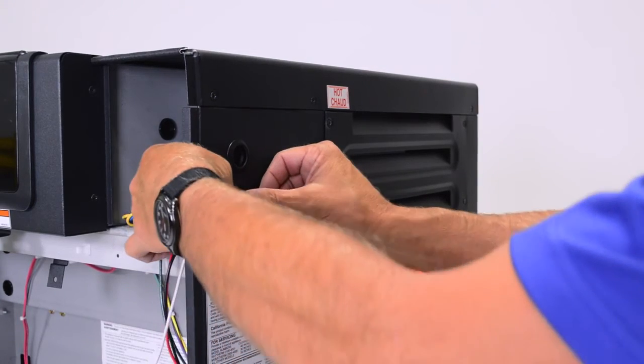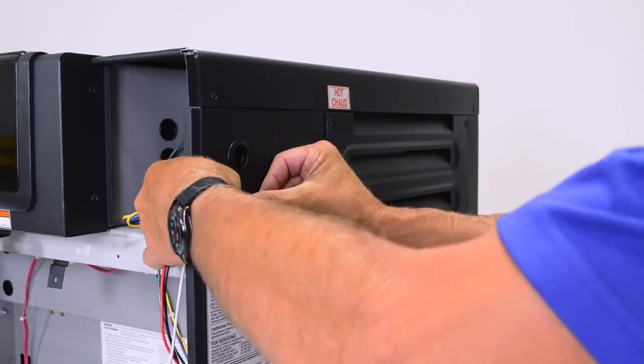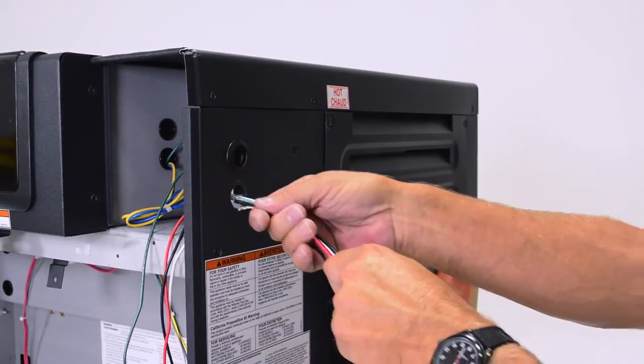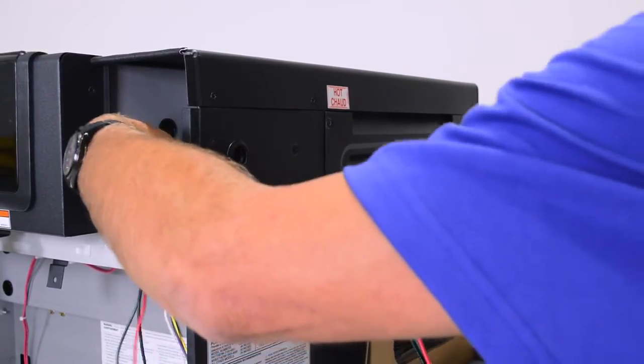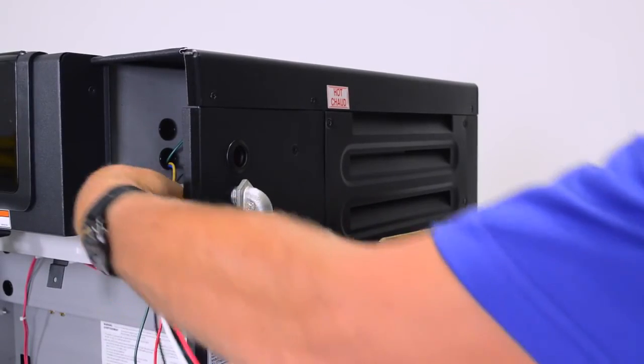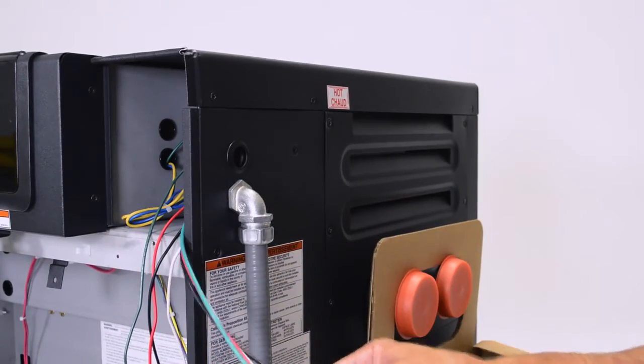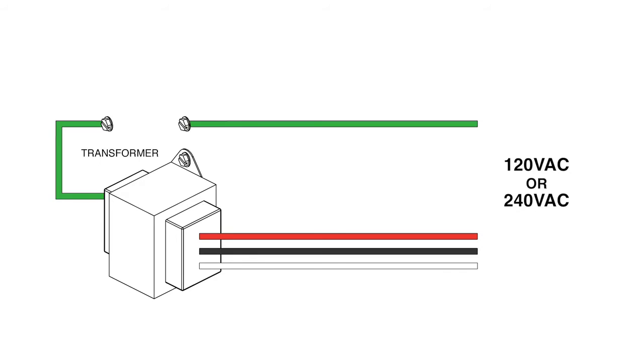Remove the lower grommet on the right side of the cabinet by pushing out from the inside. Feed wires and the 1/2 inch conduit terminal through the hole in the cabinet and secure the fitting with the locking nut. The heater may accommodate either 120 volt or 240 volt operation. The transformer must be wired differently for these two voltages.